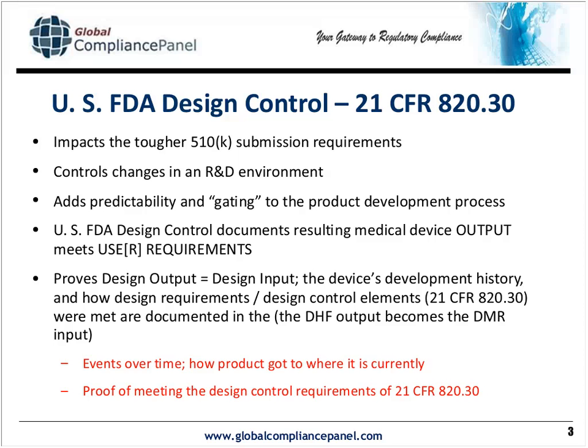One of the key requirements of design control and its documentation is that you prove by your documentation that the design, the resulting product, if you will, meets the user requirements. And when we say user and use requirements, the FDA divides the two into the patient, clinician, and also the environment, the use environment, which can be very confusing if your product is designed to be used, say, in a trauma situation, in an ER or trauma unit.